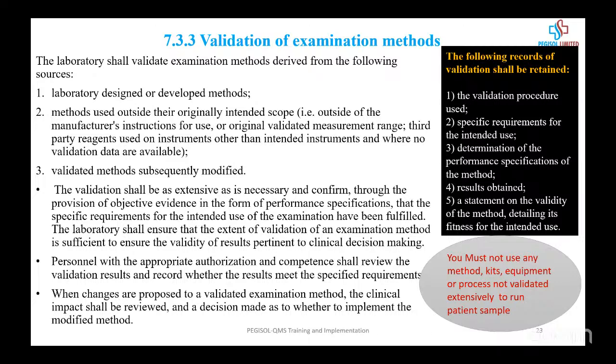So it's a commandment: thou shalt not use any method, any equipment until it has been validated. Validation is not just running about 10 samples. For quantitative testing, you will need to validate with greater than 20, because for statistical relevance, if it's not greater than 20, then for quantitative testing, statistical analysis cannot stand. Am I communicating?